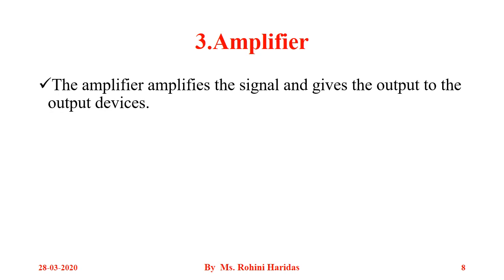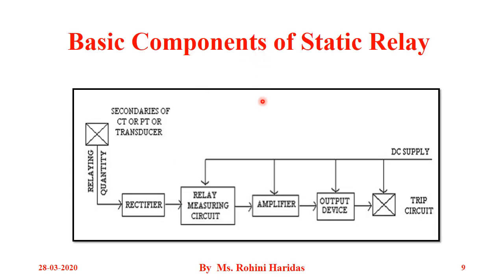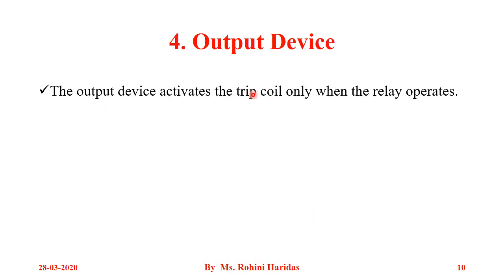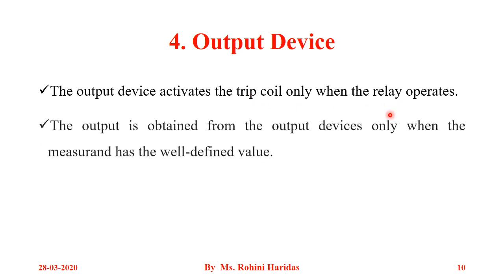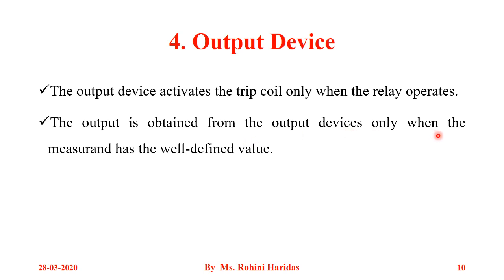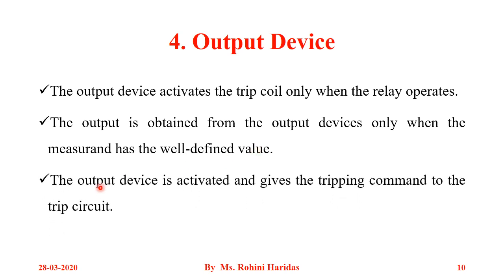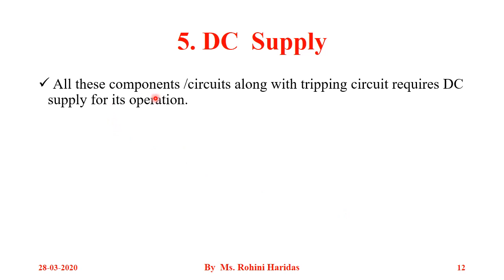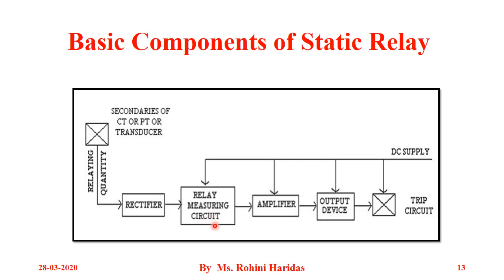The next component is the amplifier. The amplifier amplifies the signal and gives input to the output device. The output device activates the trip coil only when the relay operates. The output is obtained from the output device only when the measurand has a well-defined value, and the output device gives the tripping command to the trip circuit. All these components, along with the tripping circuit, require a DC supply for operation.